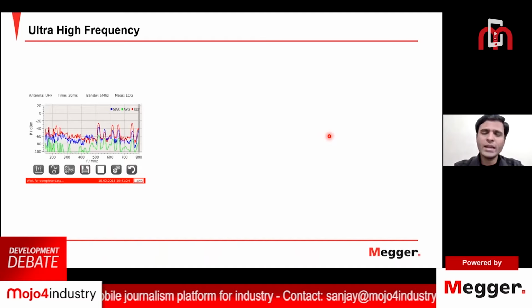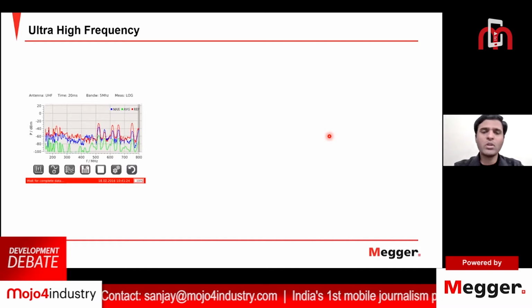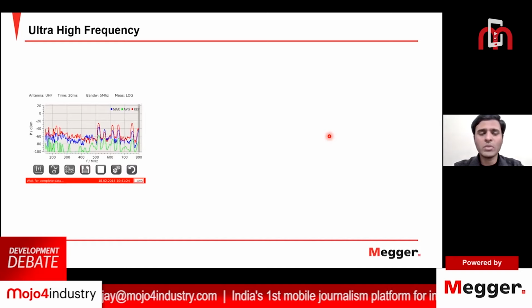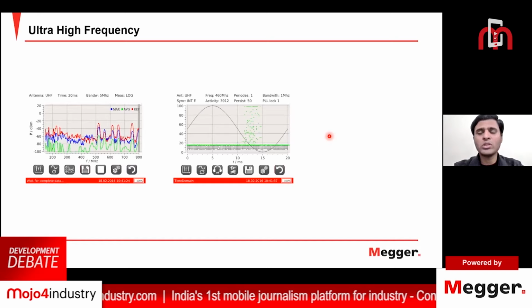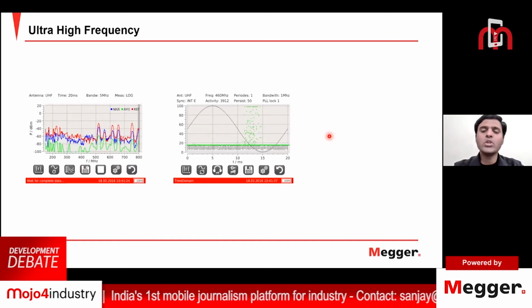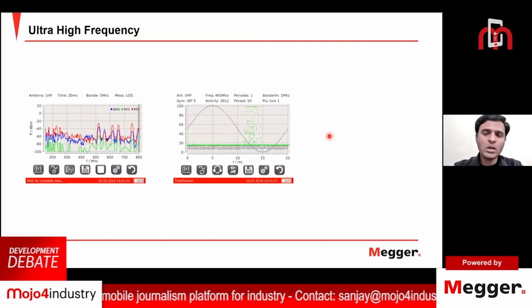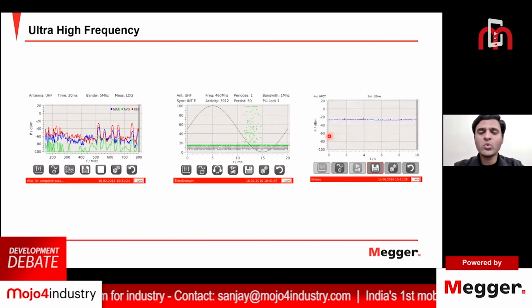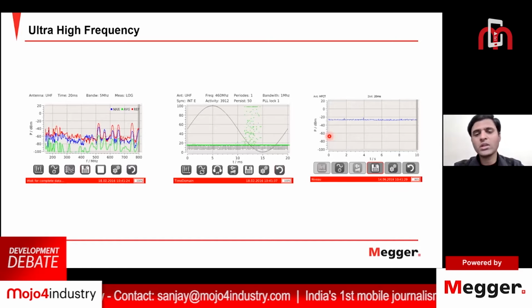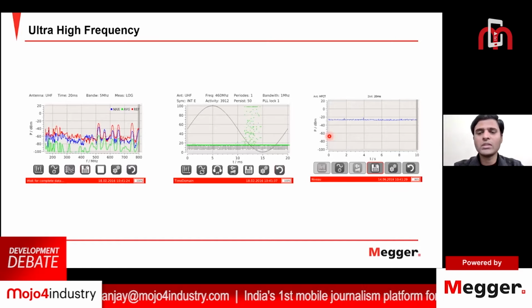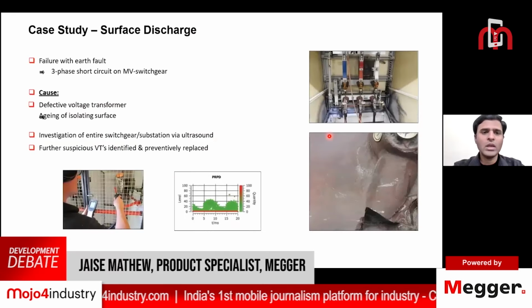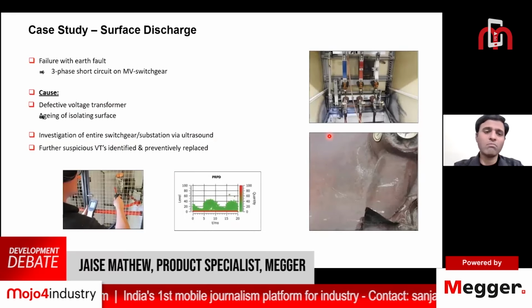However, if you want to do a detailed analysis of the discharges, the ultra high frequency technique is used nowadays, with a wider frequency range, to understand at which particular frequency a minute discharge is happening. That frequency is converted into the time domain to get a PRPD pattern, which will help you identify which type of PD it is, and if there is an actual PD, you can convert that pattern into a PD level and understand the intensity of the PD. There are some case studies in the coming slides, which Megger factory has carried out in different industries.